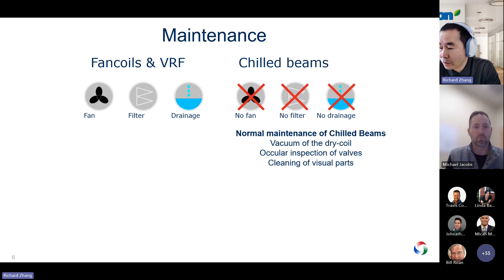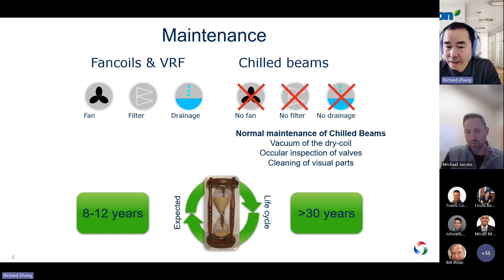So as a result, the only maintenance you really need is to vacuum the dry coil probably once per 2 years, and inspect the valve and clean the visual parts. However, there's another benefit, which is why it's appreciated and applied by many building owners. The chill beam can last 30 plus years. Going back to the reason: no fan, no filter, no drainage. By comparison, the fan coil or VRF unit can only last 8 to 12 years.